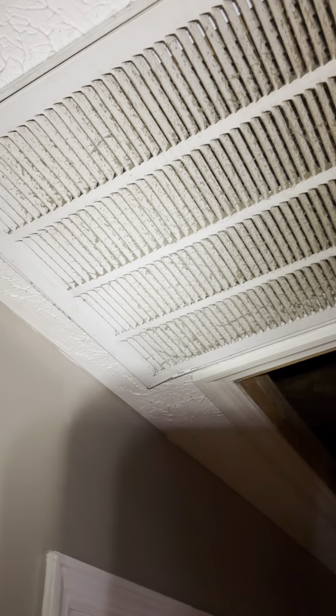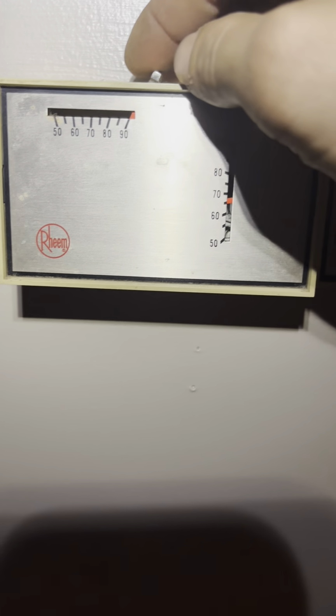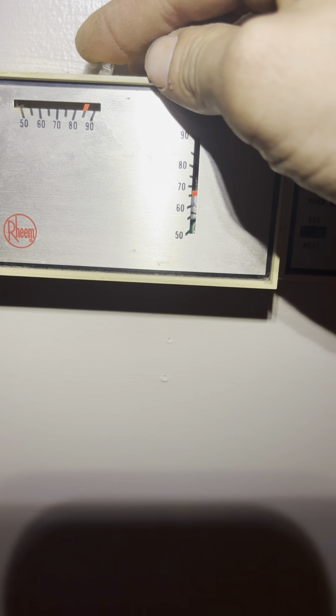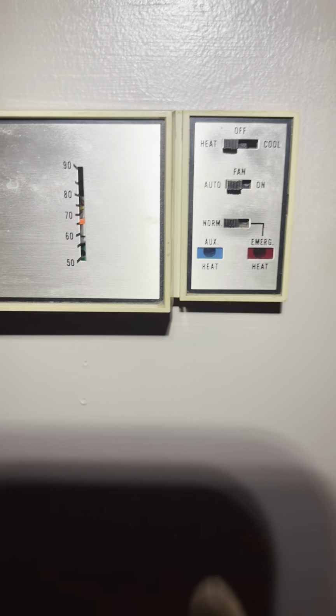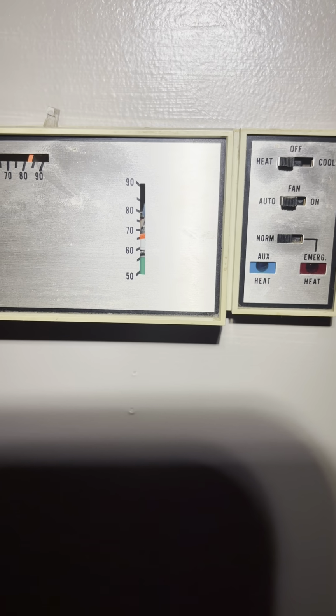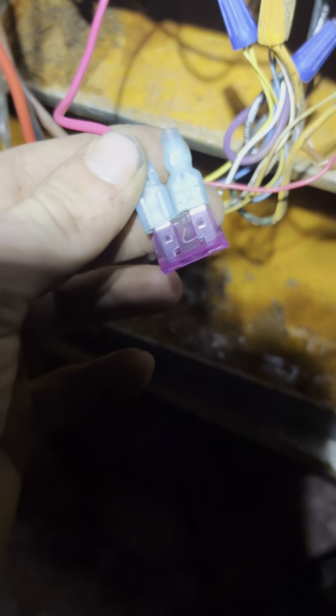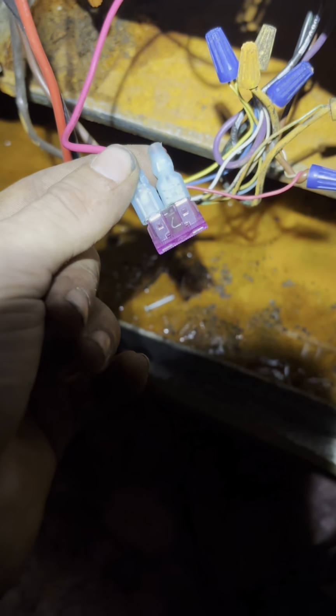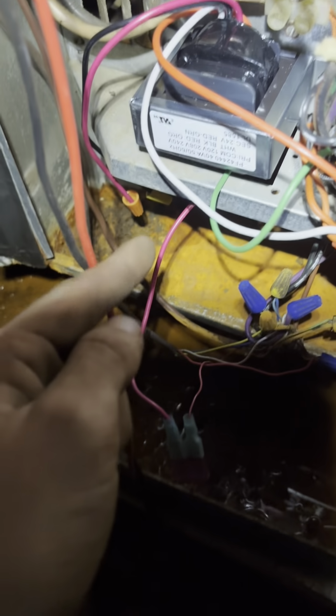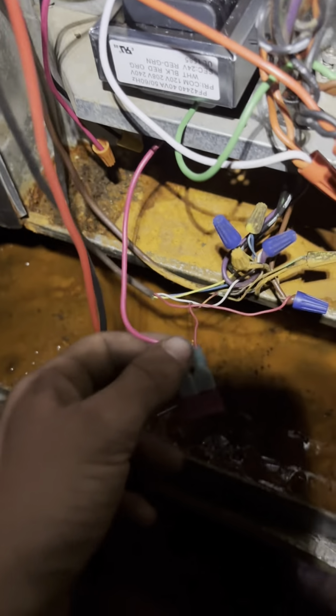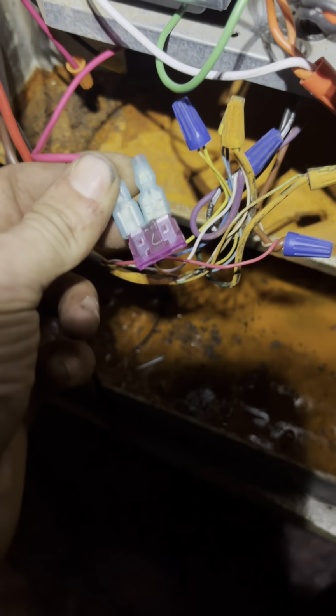All right, the unit should be powered up. So if I cut this fan switch on, it should come on. Just like that. We have now fixed the problem. Cut that off. Let's see if the heat will come on. And it doesn't. So let's figure out what's going on. All right, when I cut it on heat, y'all see the fuse has blown. And I'm glad I put this in so it didn't blow my new transformer. So now we gotta go figure out what's blowing this fuse on heat.